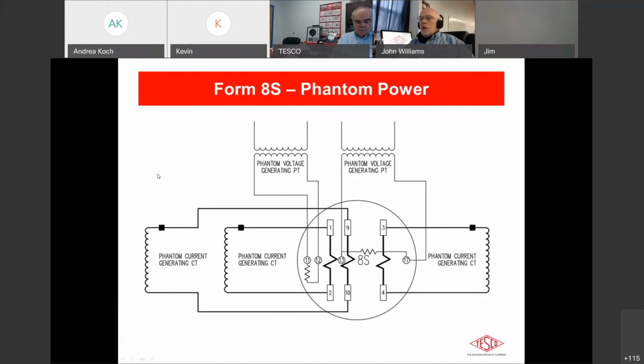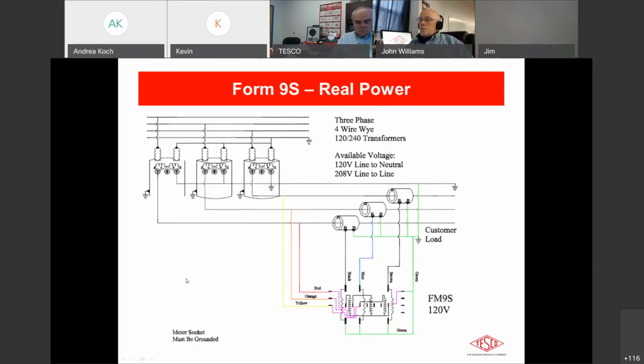Okay. And again, here, for testing purposes, the voltage transformer is going to go across basically the 240 coil here. And then we have a second one that will go across the 120 coil here, the neutral. And then the 3 current transformers going into the current elements. And of course, probably the most popular of the transformer rated forms, the 9S, typically applied to 4-wire Y circuits. In this case, we have direct voltage input and 3 current transformers.